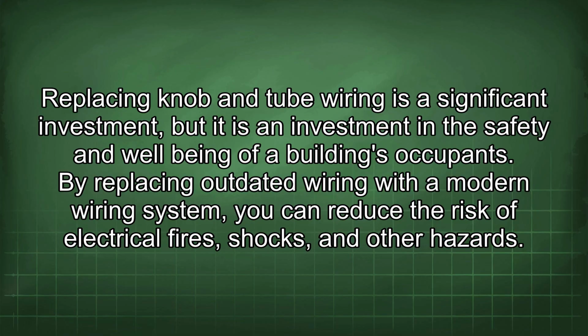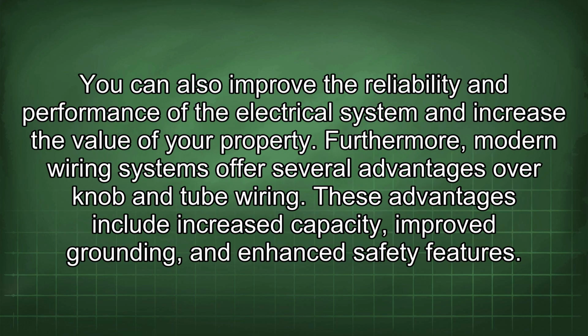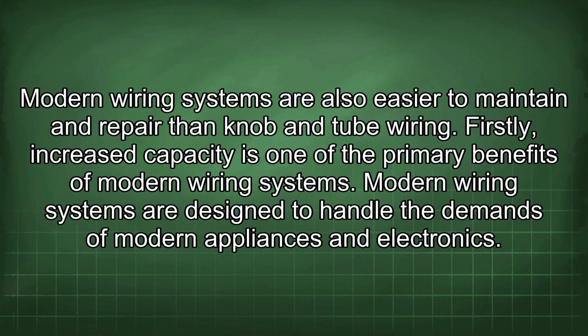By replacing outdated wiring with a modern wiring system, you can reduce the risk of electrical fires, shocks, and other hazards. You can also improve the reliability and performance of the electrical system and increase the value of your property. Furthermore, modern wiring systems offer several advantages over knob and tube wiring. These advantages include increased capacity, improved grounding, and enhanced safety features. Modern wiring systems are also easier to maintain and repair than knob and tube wiring.